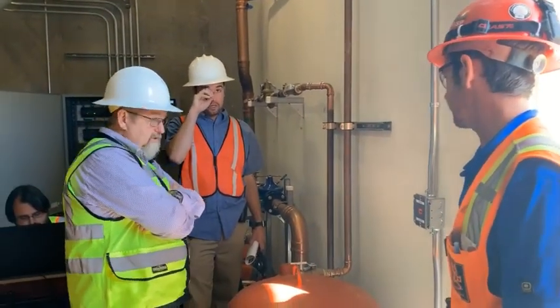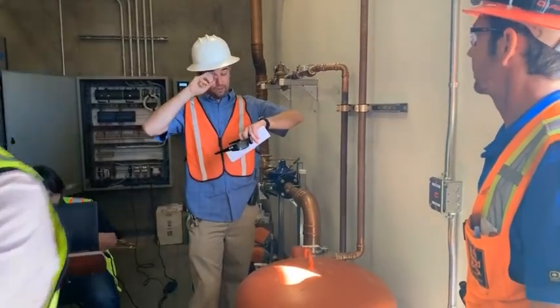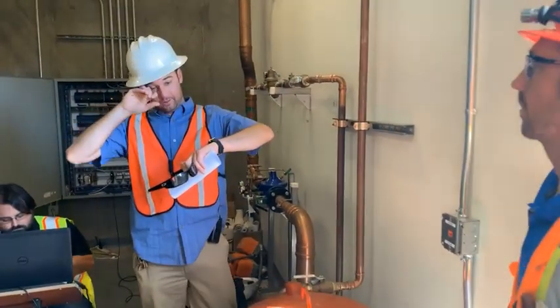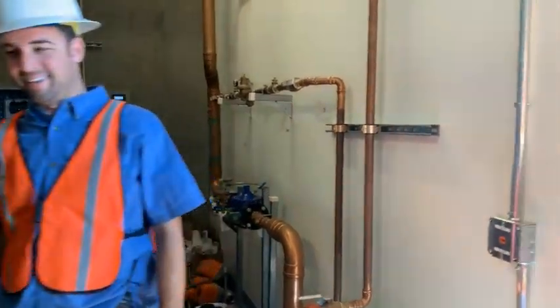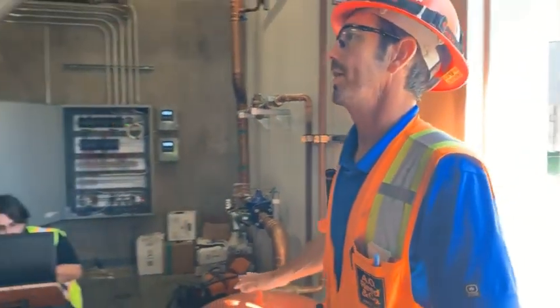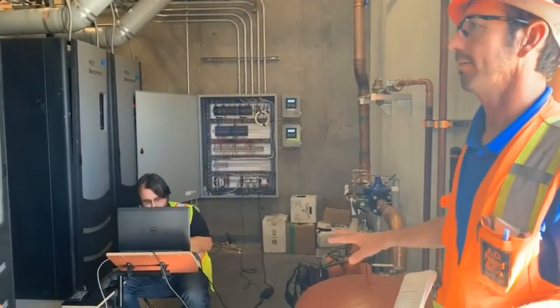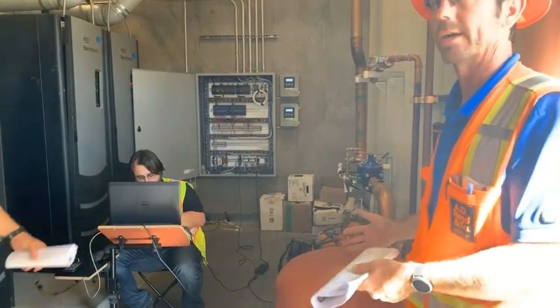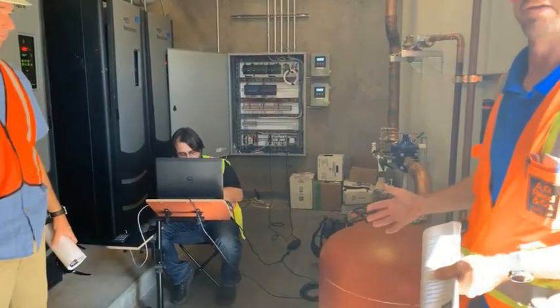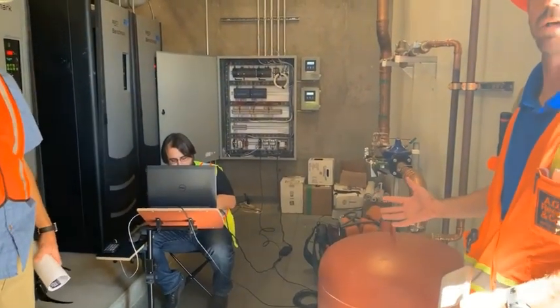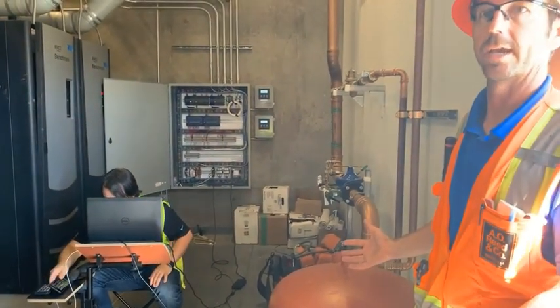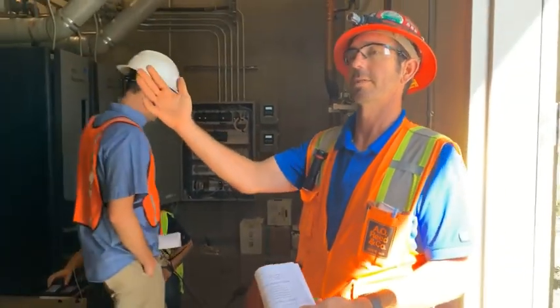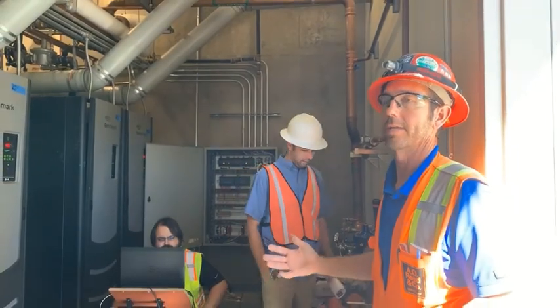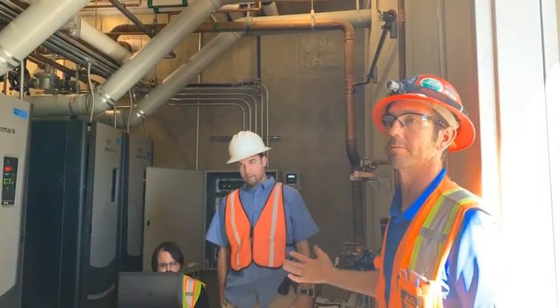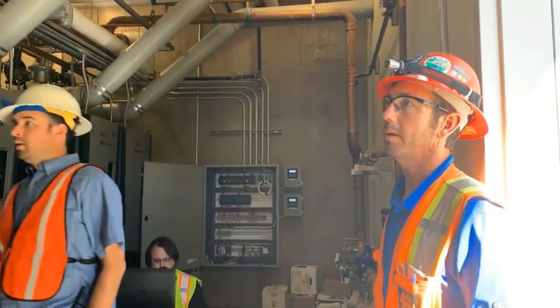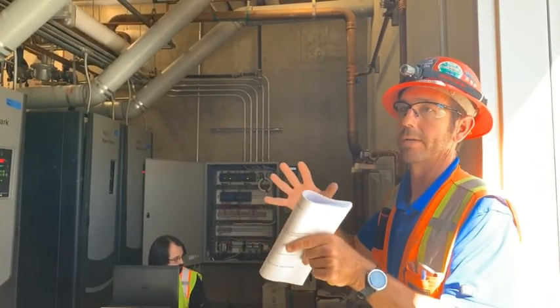I'm not gonna say that we do that on our buildings that we have now, but I do recommend doing that. Now that I know, someone told me that if the tank fills, because it's a bladder, and this fails and it gets waterlogged, it's like having no expansion tank. And if a heat exchanger or something goes out of whack, it has the potential of blowing that apart. You'd hear a knocking noise when it goes bad? It could be that too, but it could be a slow increase of pressure, and then it can.